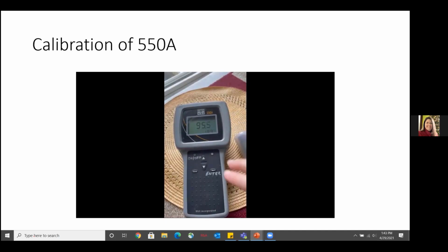The next step in calibration is to hit both the down arrow and the up arrow at the same time. When you do that, you will get CAL for calibration. You then hit enter. Once you hit enter, a number will come up. This is where you will enter the elevation of where your lake is. In the Lansing area, the elevation is about 900 feet.